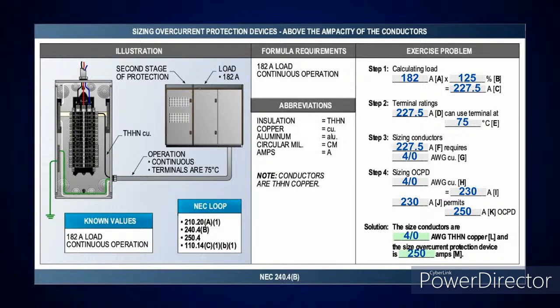Now, one of the things I brought up, and we just showed a good example of this earlier: if I did a calculation and came up with, say, 58 amps, and I look at table 240.6A, what's the next size overcurrent device above that? A 60 amp. But if I look at table 310.16 and pick the wire size, the next size above that 58 amps is 65 amps, which is a number 6 conductor. Well, I can either protect the load or that conductor, because it didn't match up with the overcurrent device. So what's the next size above that 65 amps? That's a 70 amp. So I could use a 60 or 70 amp. That's how you're going to apply 240.4B.